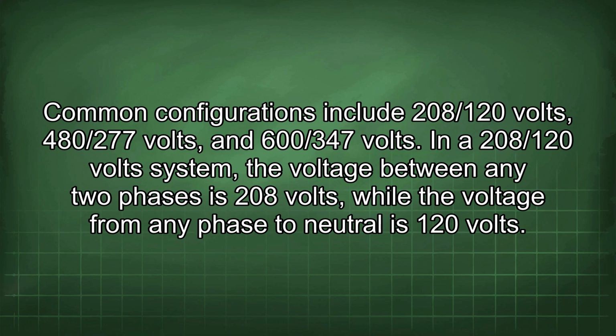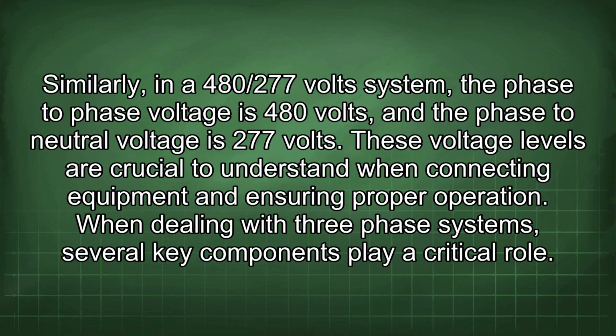208/120 volts, 480/277 volts, and 600/347 volts. In a 208/120 volt system, the voltage between any two phases is 208 volts, while the voltage from any phase to neutral is 120 volts. Similarly, in a 480/277 volt system, the phase-to-phase voltage is 480 volts, and the phase-to-neutral voltage is 277 volts. These voltage levels are crucial to understand when connecting equipment and ensuring proper operation.